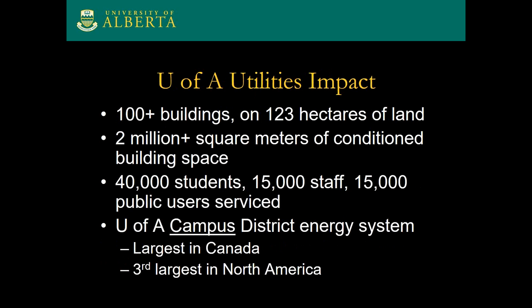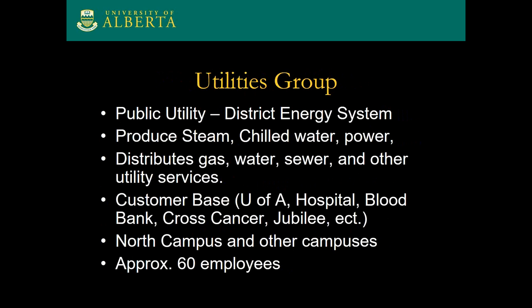So in terms of a campus district energy system, we're the largest in Canada, and we're the third largest in North America. For the utilities group itself, we are a public utility. We have a district energy system, as I've mentioned. We produce on-site steam, chilled water, and power. We produce steam from burning natural gas. We distribute through the services corridor gas, water, sewer, and other utility services as flow through. The sewer is not in the corridor itself. It's below. It's deeper than that.